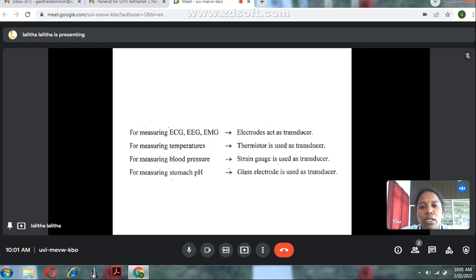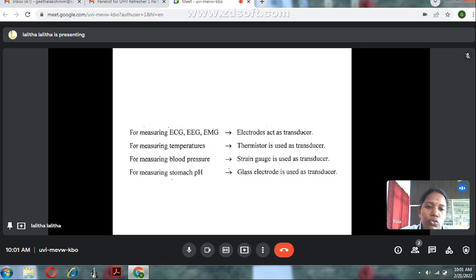For measuring ECG, EEG, and EMG, the electrodes act as a transducer. For measuring temperature, a thermistor is used as a transducer. For measuring blood pressure, a strain gauge is used as a transducer. For measuring stomach pH, a glass electrode is used as a transducer.